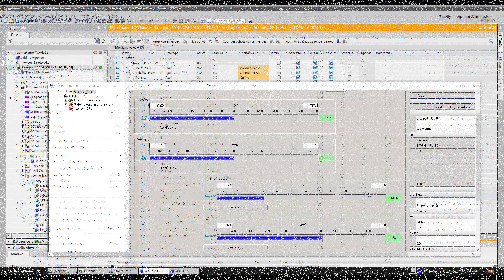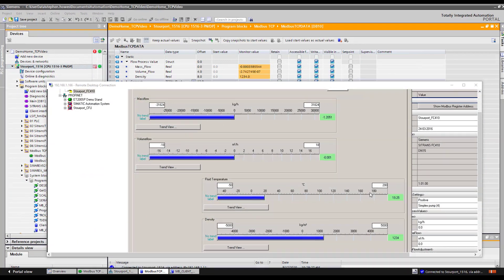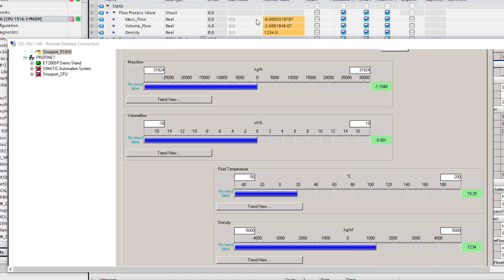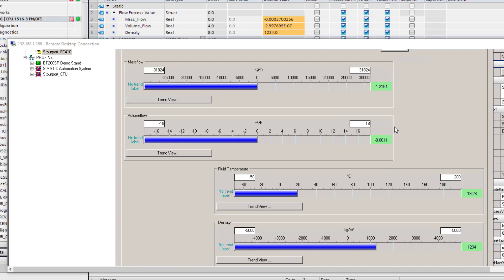Once you have performed a download, if you remember you can see on this screen I have got my data block up here. There is my process values. Now the units on these are kilograms per second and meters cubed per second, and here we have kilograms per hour and meters cubed per hour. So this is why these are moving a lot more, they are much smaller values. But you can see they are updating. I have got two masters connected to one Modbus device. I have got the temperature there and there is my simulated density to prove that it is all working. One two three dot four. We are reading it as a float so it has put the decimal point in.